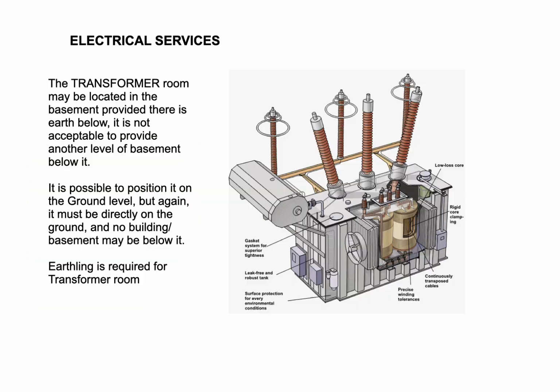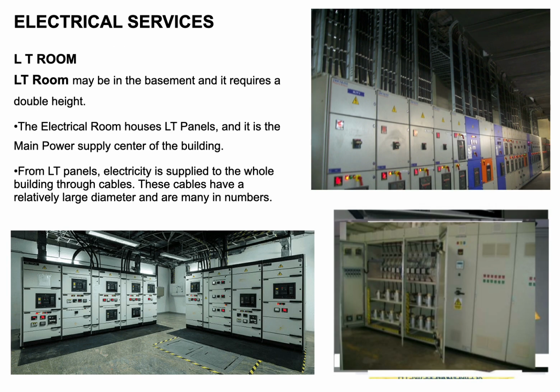The transformer room may be located in the basement provided there is earth below. It is not acceptable to provide another level of basement below it. It is possible to position it on the ground level, but again, it must be directly on the ground and no building or basement may be below it. Earthing is required for the transformer room. Now, the LT room may be in the basement and requires a double height.